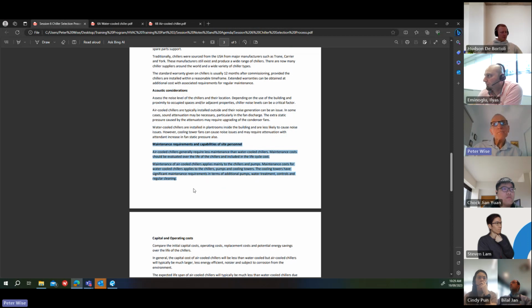Maintenance needs to be considered. And some projects have site personnel employed to carry out maintenance on mechanical plant. Some of those people, you need to understand the capabilities of those people, whether they can look after the chillers. Air-cooled chillers generally require less maintenance than water-cooled chillers. Maintenance costs need to be evaluated over the life of the chillers and included in your life cycle costing.